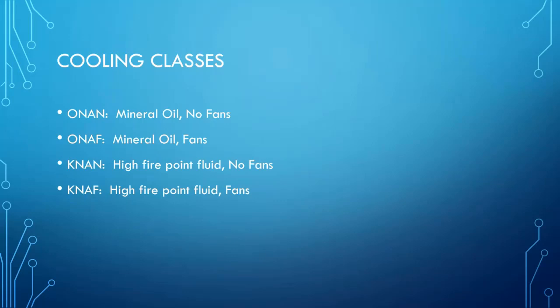In a previous slide, we used some terms. I'd like to more clearly define those. The ONAN class refers to a mineral oil filled transformer that does not have fans. An ONAF rating is a transformer that is filled with mineral oil and has fans. A KNAN transformer is filled with a high fire point fluid and does not have fans. And a KNAF has a high fire point fluid and has fans.